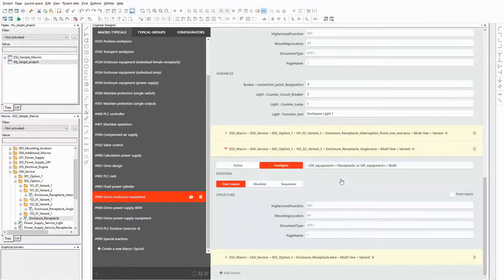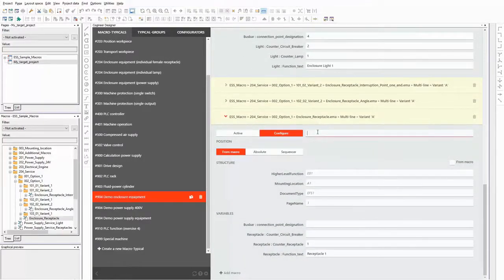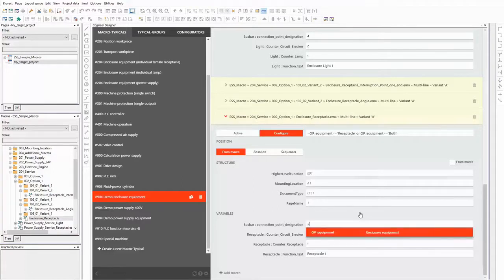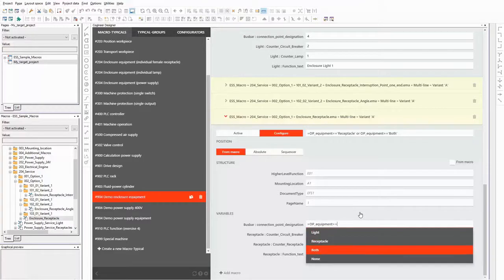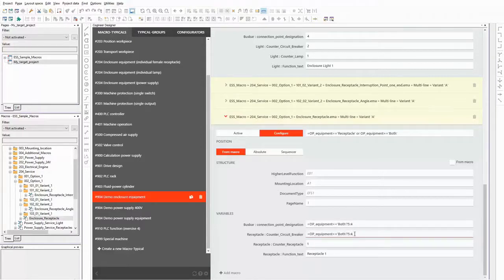In the detailed view of the macro that contains the receptacle itself, you can see the variables of the placeholder objects. This time I need a condition here, otherwise I would have the same device tag twice in the schematic. I can set this up by using an if-then-else condition. If the value both is selected, then the counter should be 5, else it should be 4, like for the enclosure light. I can use the same condition for the counter of the circuit breaker. But this time the counter should be 3 instead of 2 when the value both is selected in the configurator.